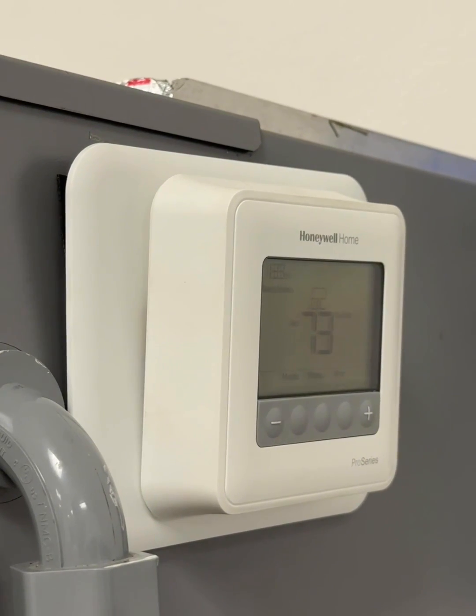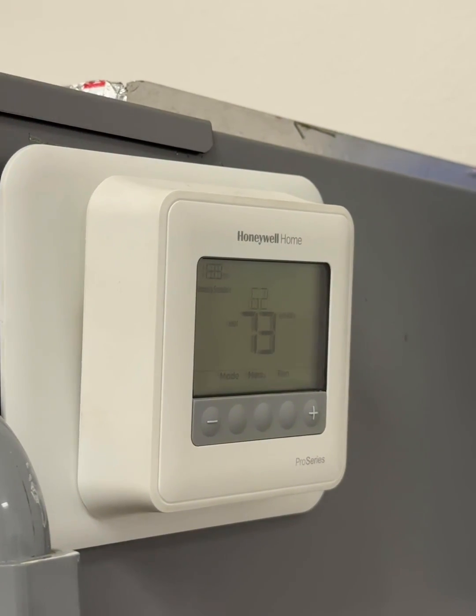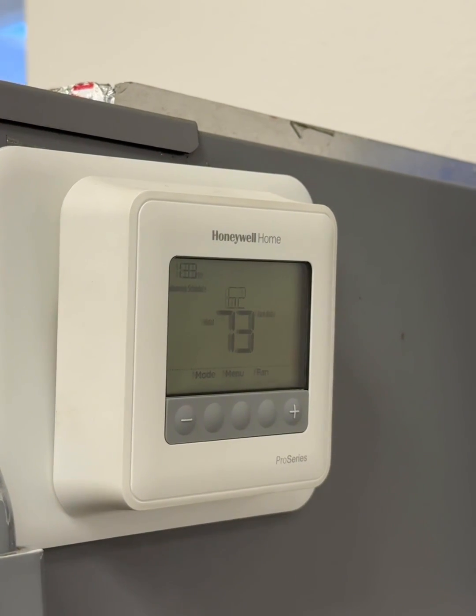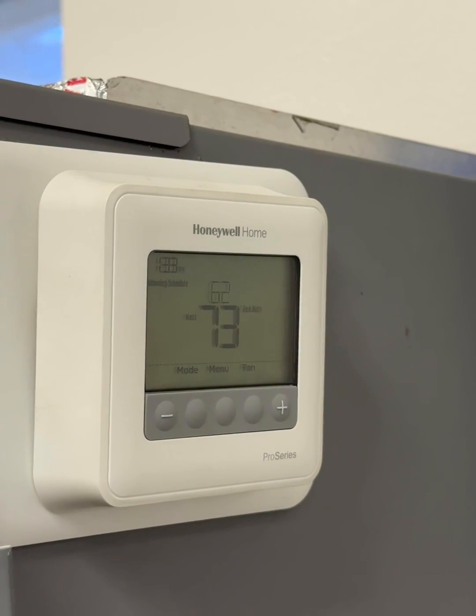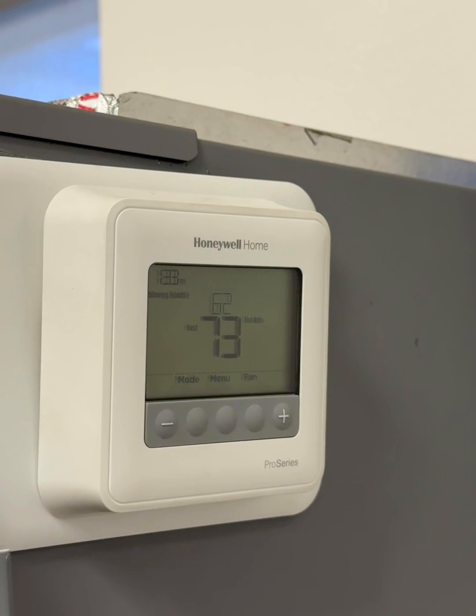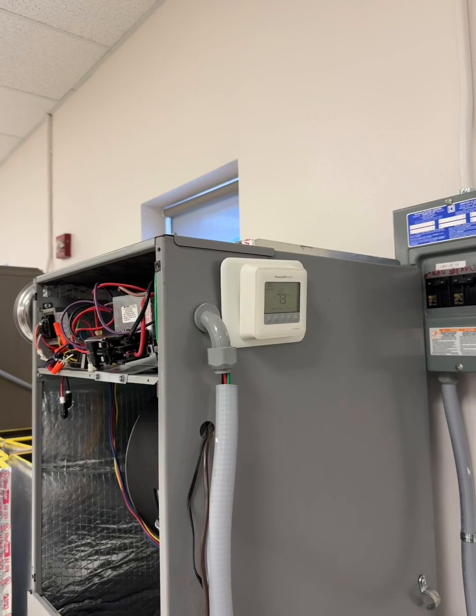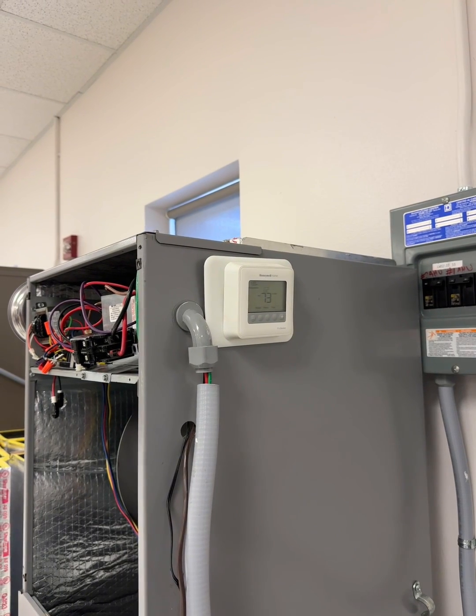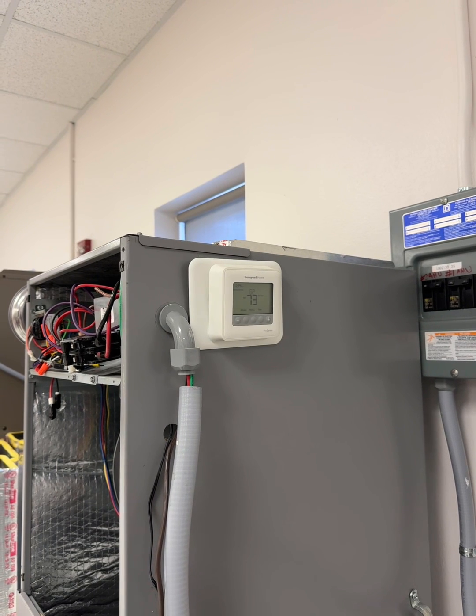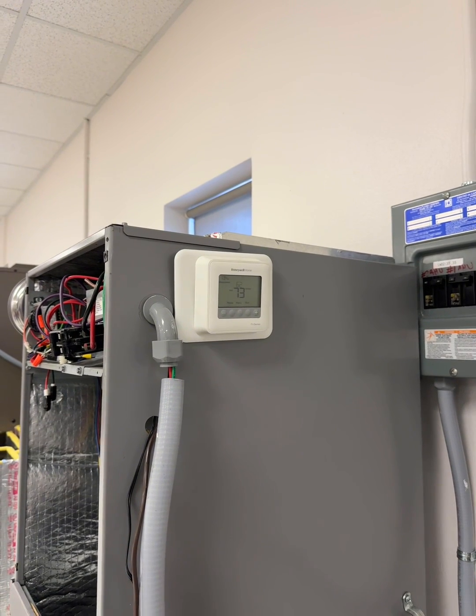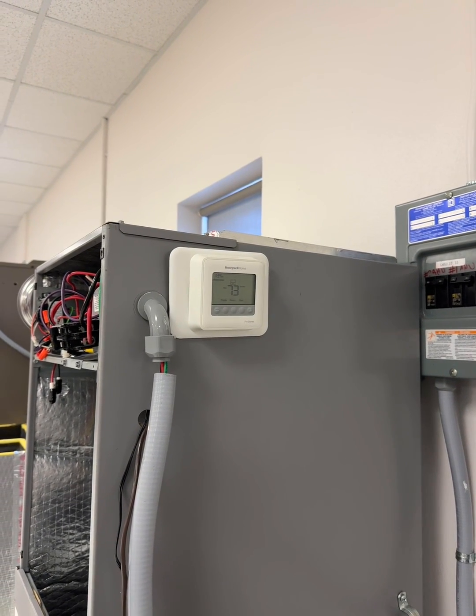The thermostat closes the cooling contacts. Then it sends the 24-volt signal to the compressor contactor in the outdoor unit and the blower relay in the air handler. The system runs until the room cools to the set point, and then the thermostat opens the contacts once the set point has been reached.